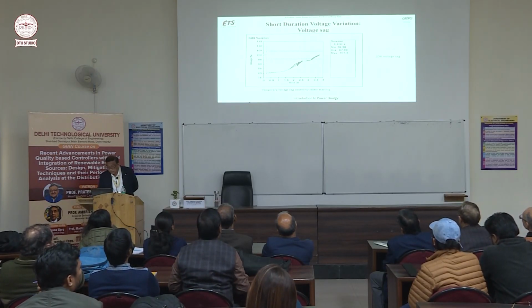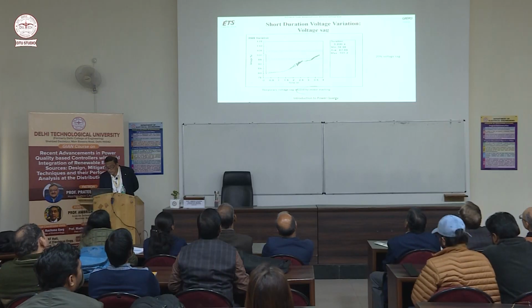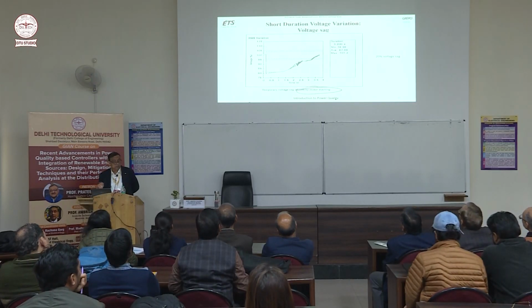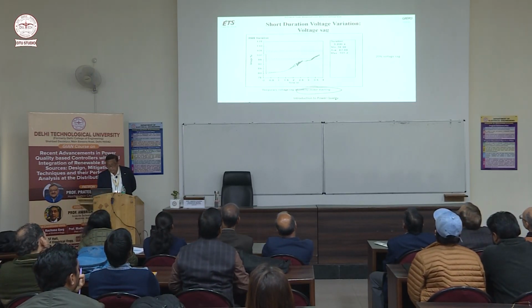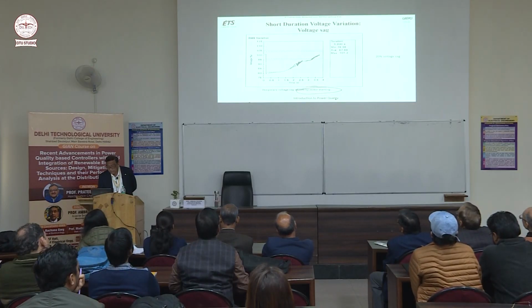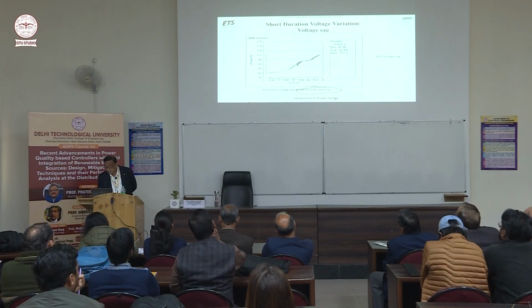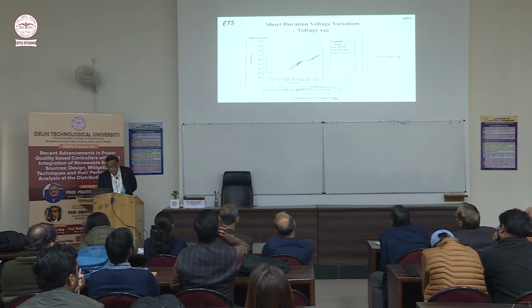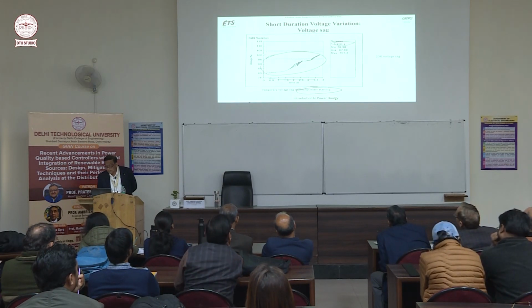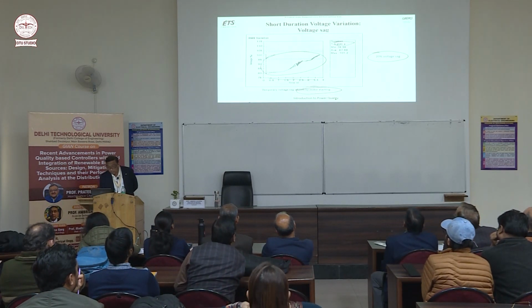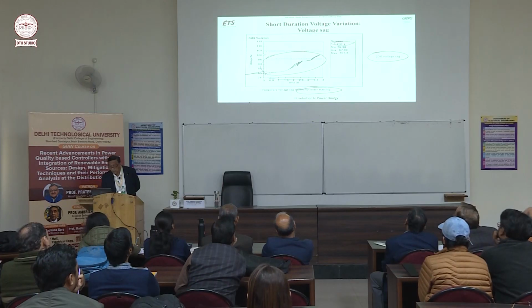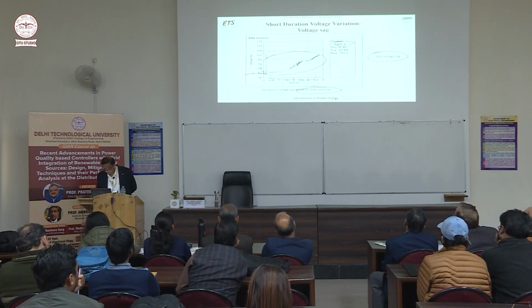And this is the voltage sag caused by motor starting. As I was telling you, if you have a large induction motor, then for a few seconds, like in this case 3.2 second, you have a voltage sag here, a 20% voltage sag because the voltage has gone down to 80% here.